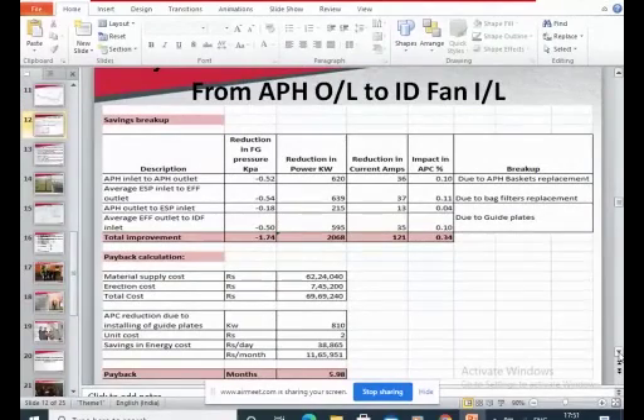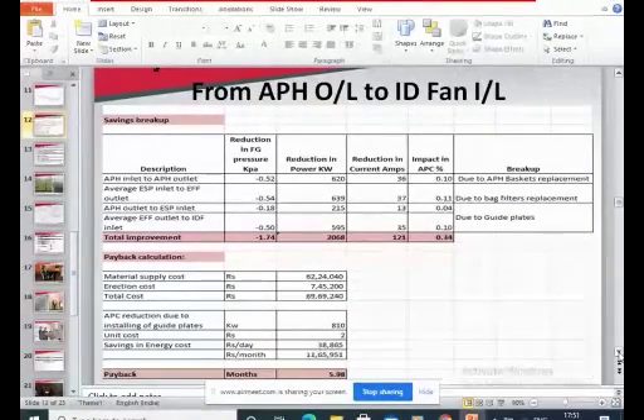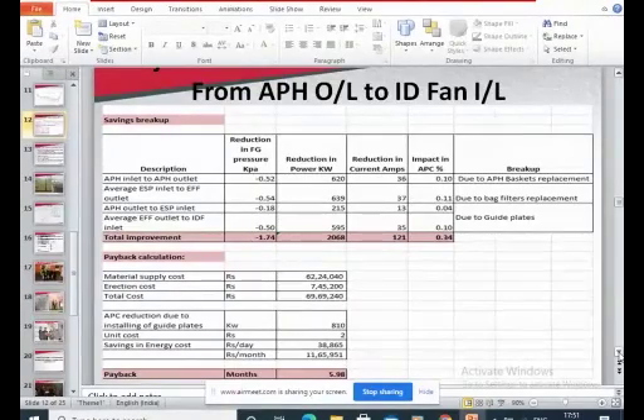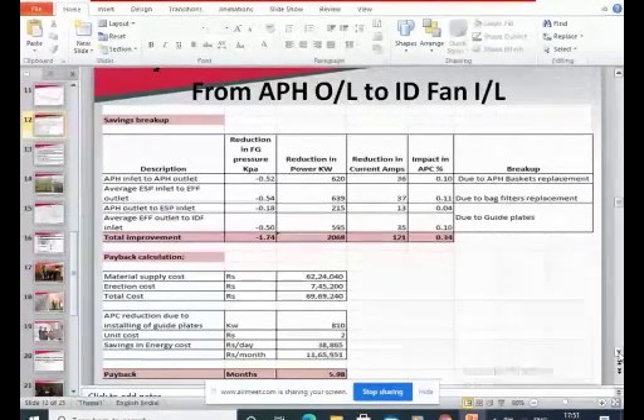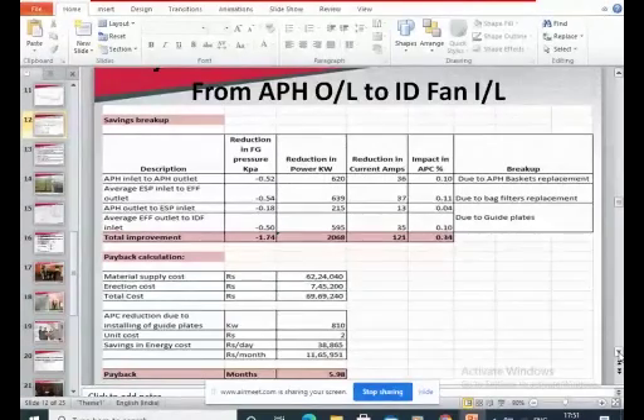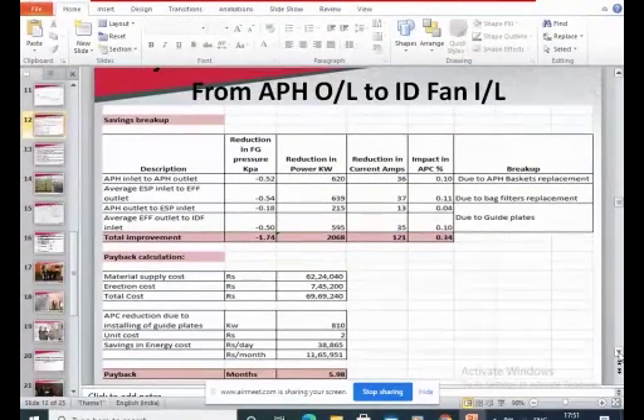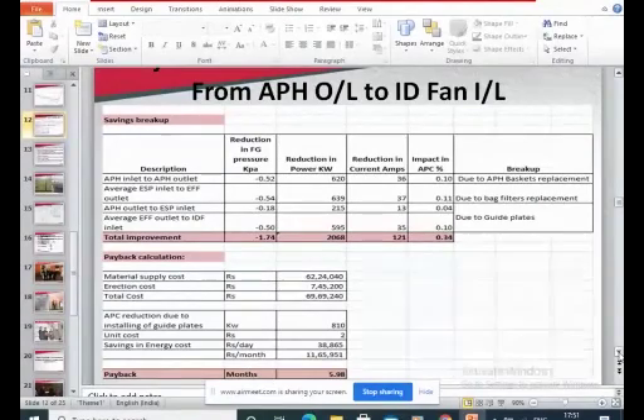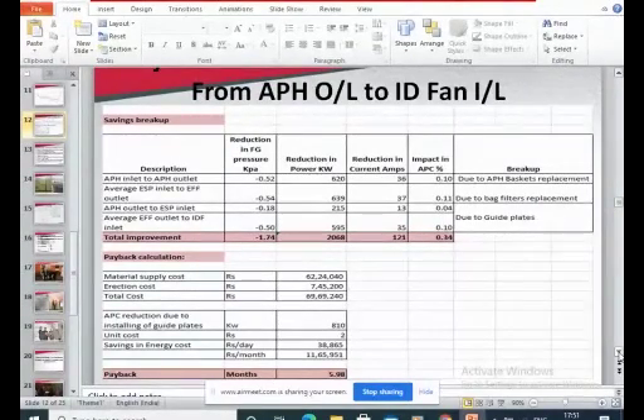The entire exercise was carried out for power consumption, because this took an outage of 20 days, and in that time most of the other things were also carried out in the boiler. So the total pressure drop was reduced, and we identified this as a total ampere reduction in the ID fan, and we found that approximately 810 kilowatt of power was saved.